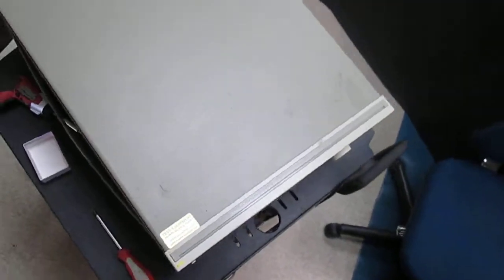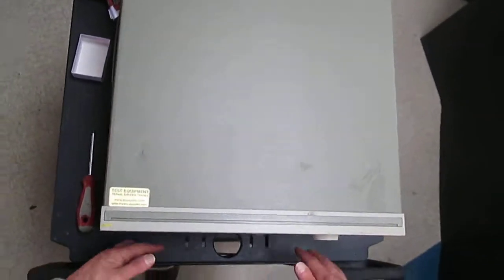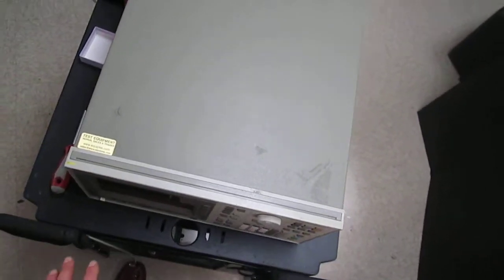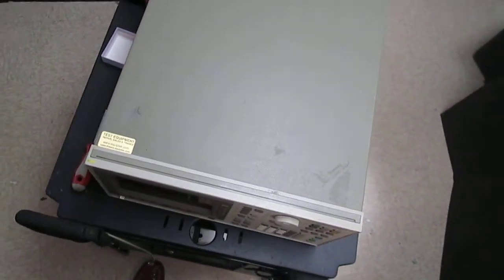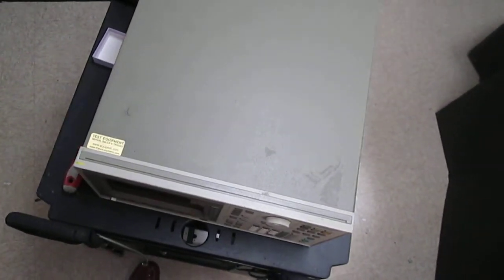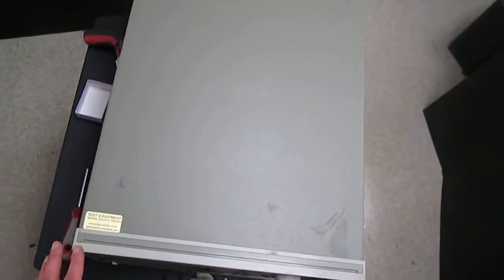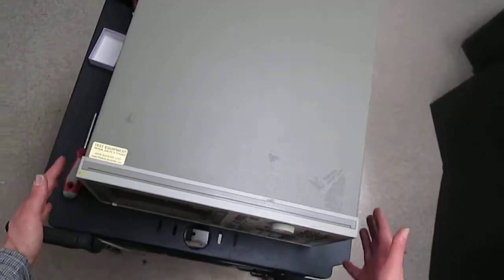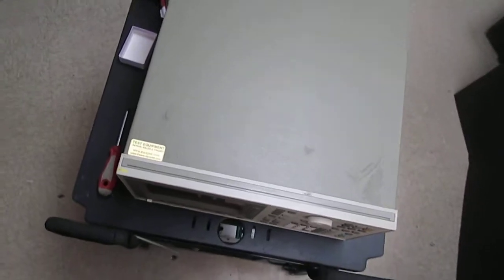Let's unplug the analyzer. The good place to do this procedure is a long table where there is plenty of room, so when you open the front panel it doesn't fall off the table. I'm going to use a cart, but I strongly recommend you use something longer than what you see in this video.